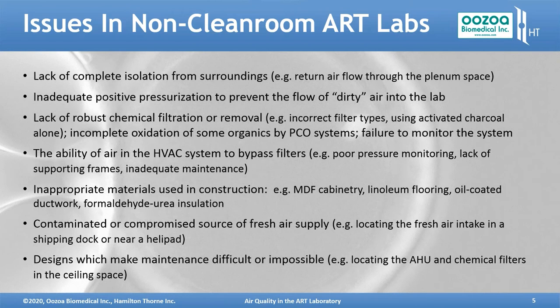We have inadequate positive pressurization to prevent the flow of dirty air into the lab. Positive pressurization is always greatest in the embryology lab, so that there's always an outflow of air from the embryology lab, not an inflow of air from other areas, even within the clean room. If you don't have a clean room lab, you typically will have insufficient or non-robust chemical filtration or removal due to incorrect filter types or using activated charcoal on its own.